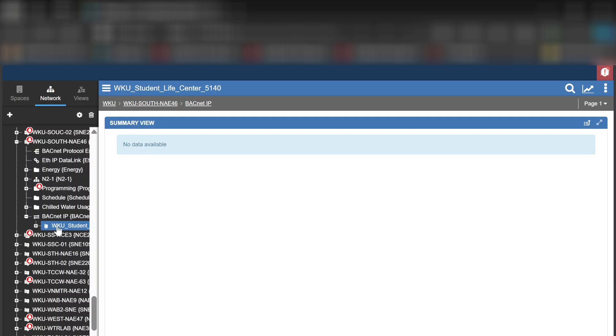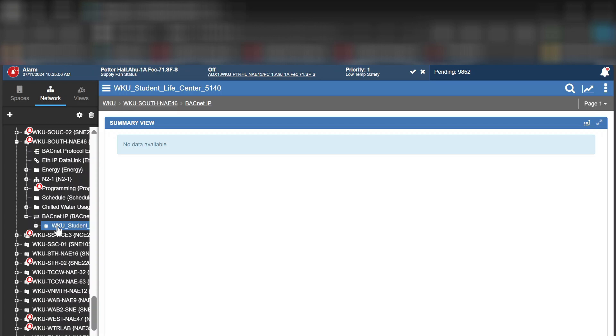Make sure you pull them in right the first time. Now we're going to jump into our Metasys system — we're running Metasys MUI. We can see the Jace is already populated on our network. There are actually four air handlers that are part of this, and what I want to do is add a couple of folders. One of the problems with trying to pull all the points in at once is you can only display so many points within Metasys — if you don't break it up, you won't be able to see all your points.